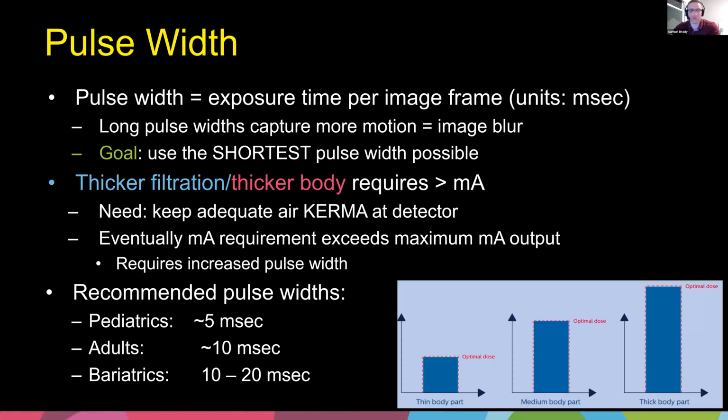Some of them are no better than they were in the olden days. They're a little better, but not that much better. And so we're constantly telling them to turn that down, turn that down. Your more high-end interventional systems will have these values down closer to 5 and 10. And the same for your general fluoroscopy, your table tilt systems. But this is just a rule of thumb, but this is what I typically always tell them to do.